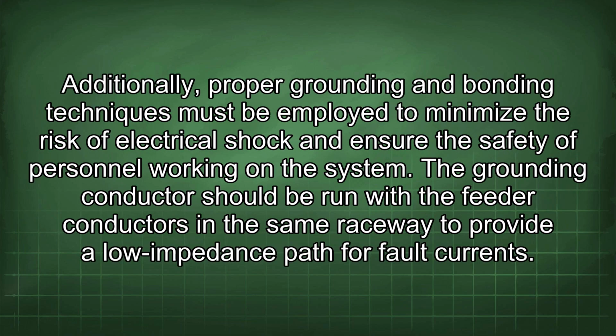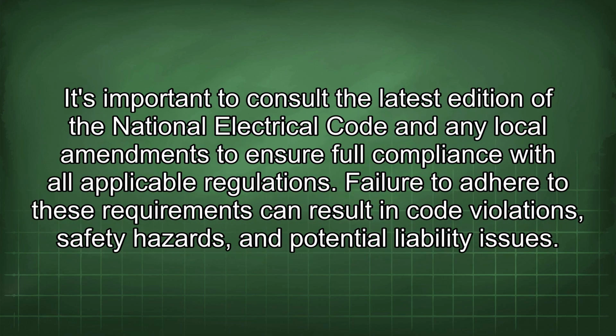Additionally, proper grounding and bonding techniques must be employed to minimize the risk of electrical shock and ensure the safety of personnel working on the system. The grounding conductor should be run with the feeder conductors in the same raceway to provide a low impedance path for fault currents. It's important to consult the latest edition of the National Electrical Code and any local amendments to ensure full compliance with all applicable regulations. Failure to adhere to these requirements can result in code violations, safety hazards, and potential liability issues.